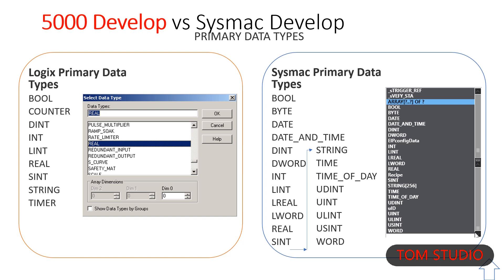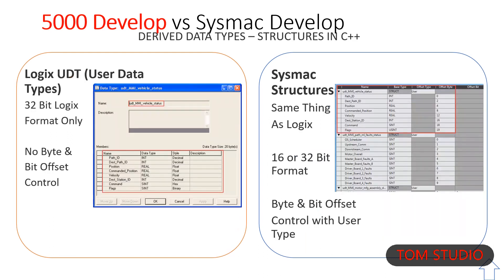Structures are the universal term for derived data types. AB calls them UDTs. Omron's 32-bit format is almost exactly like Logix. To duplicate exactly, we use the user offset type. Bytes have to match up exactly for CIP read/write to Rockwell.